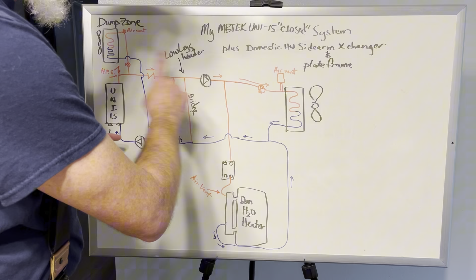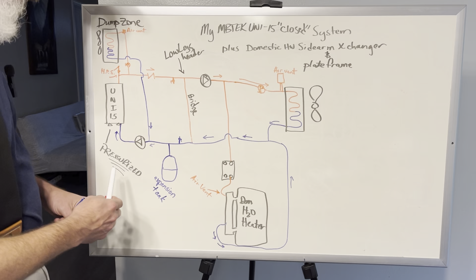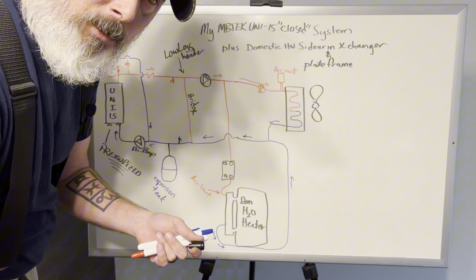I'm sorry about the layout. This is obviously not what it looks like at my house, but this is how it's piped in. I'll try to go in as good an order as I can. So let's just do it. This is a primary pump here. I'm pumping to the boiler, which is different than what I did on the open system. There will definitely be a lot of explaining, but because of how I wanted this safety zone to work and give me heat during normal operation, I did it that way. Basically, return water comes into the boiler, goes through the boiler, and gets heated.